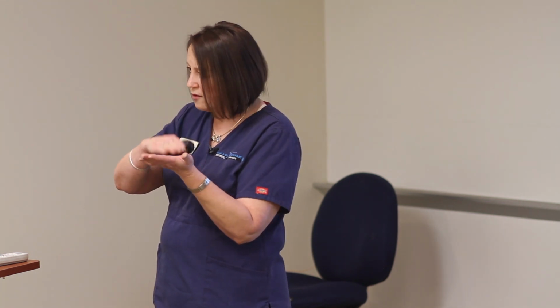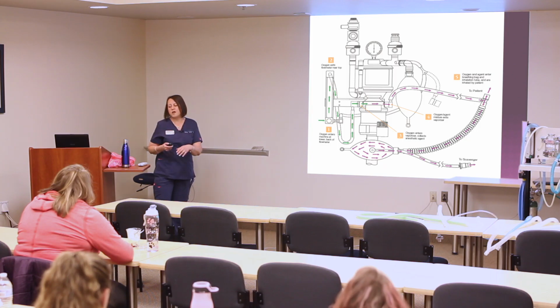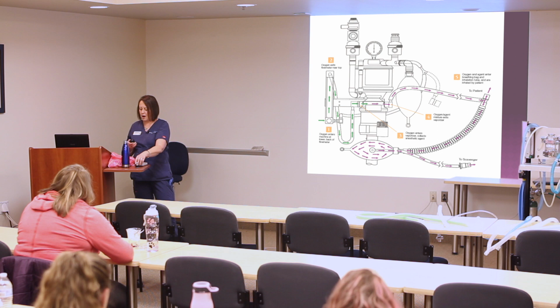And those flutter valves, if you look on these machines, if they've been used for a really long time, you probably notice that there's a lot of moisture that can even sit right on top of that flutter disc. And every time there's a lot of moisture in there, that is also going to make it harder for any animal to move that flutter valve and to breathe. So it's important, if you see moisture sitting on top of those discs, that you take it apart and take the time to clean those out and dry those out, which would be more of an issue on the matrix machine in the operating room.